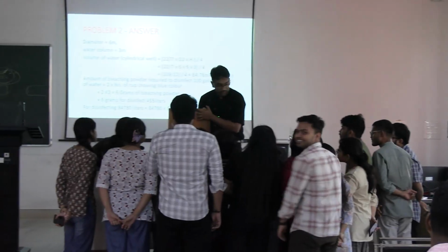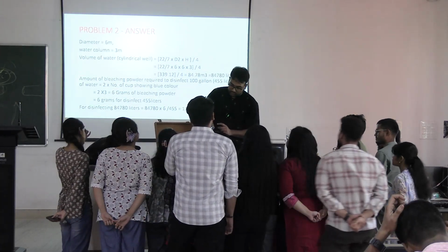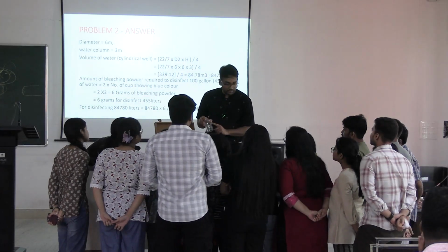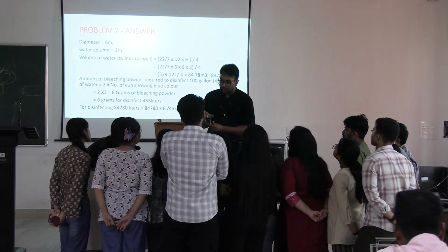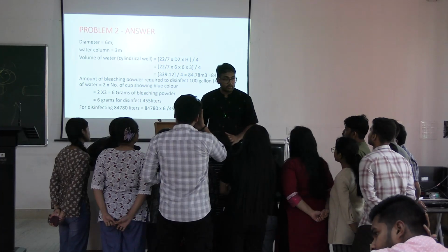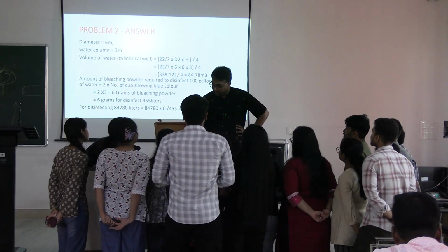So this is your Horrock's apparatus. কি কি রয়েছে দেখ, এখানে 6টা গ্লাস রয়েছে, ট্রান্সপারেন্ট গ্লাস, যেগুলোতে ক্লিয়ারলি এখানে মার্ক করা রয়েছে। তো আমরা 200 ml পর্যন্ত জল ভর্তি করি এগুলোতে, right? Then this is your colored glass to prepare the bleach solution, isn't it? So what we do initially before doing the chlorine demand estimation, we need to know 2 things. First, we need to see that the water is free from turbidity, and secondly that the pH is between 6 and 7.5.